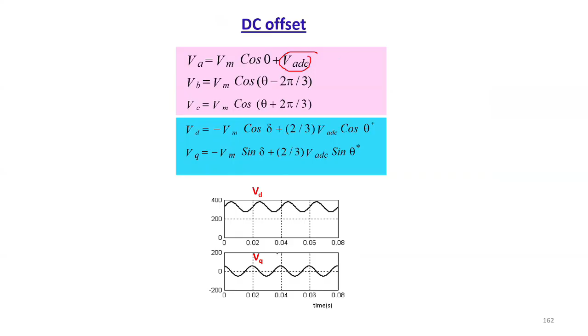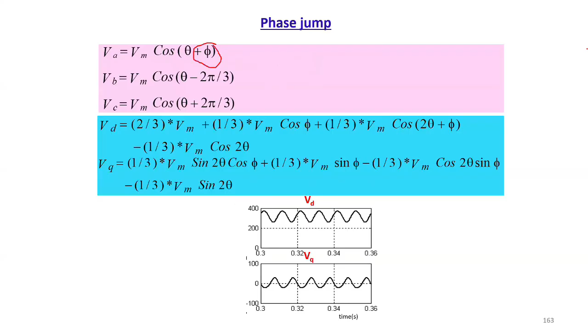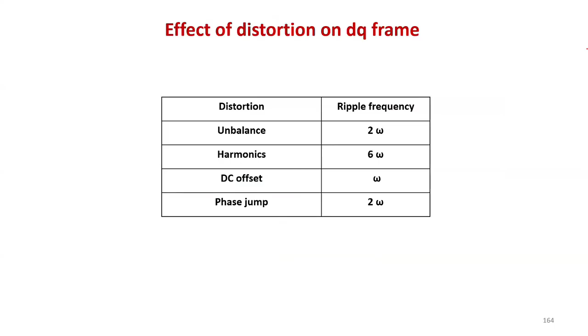Similarly, a DC offset has been added at phase A, and the corresponding VD and VQ is observed - it is not uniform. A phase jump was also introduced, and tests were done with respect to that. So we observed the effect of distortion on the DQ frame: unbalance, harmonics, DC offset, phase jump, and the corresponding ripple frequency, how much it will be - that also we check.